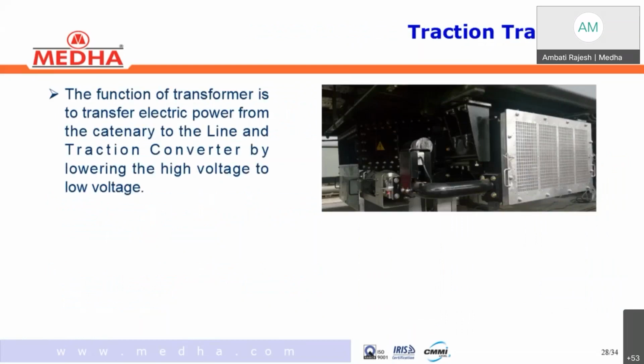Next, the traction transformer. This traction transformer is in our scope of supply, but we are not manufacturing it. We are taking it from outside, ABB and Siemens. In MEMU, in general, ABB and Siemens make oil cooled 1250 kVA rating traction transformers are placed, with a radiator mechanism to cool the oil. There is an oil pump and cooling blowers, with all these facilities provided with this traction transformer. The main function of this traction transformer is to step down the OHE voltage of 25 kV into 950 volts.